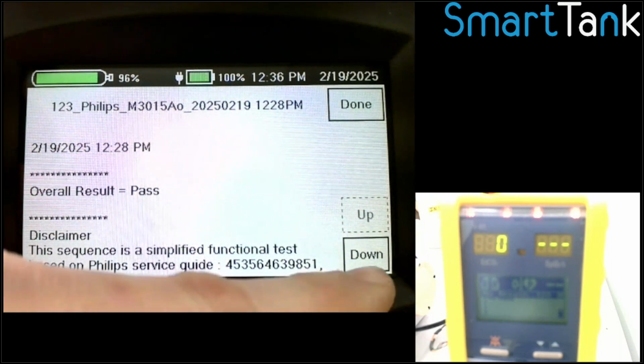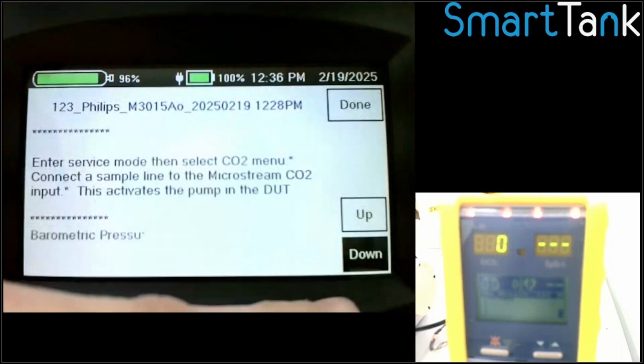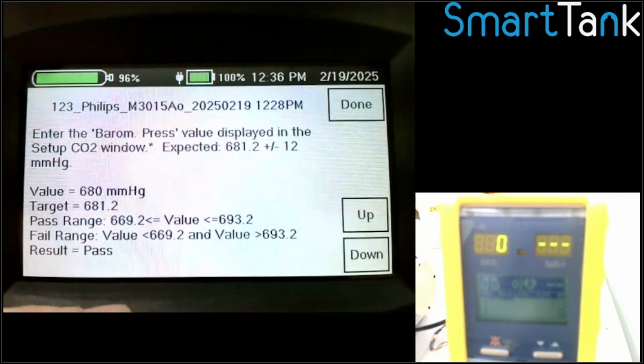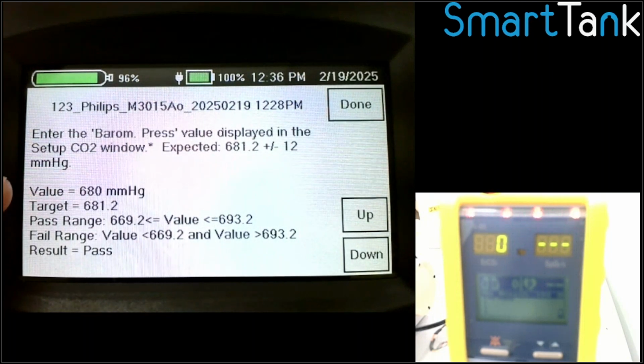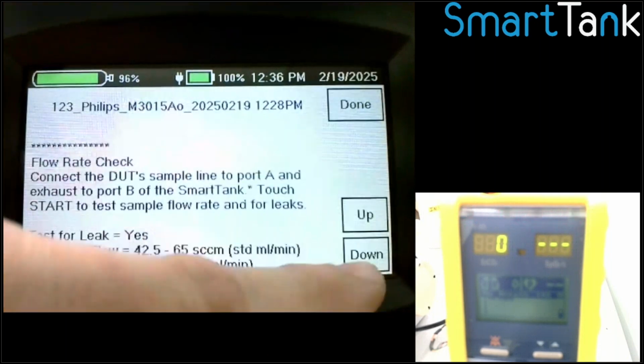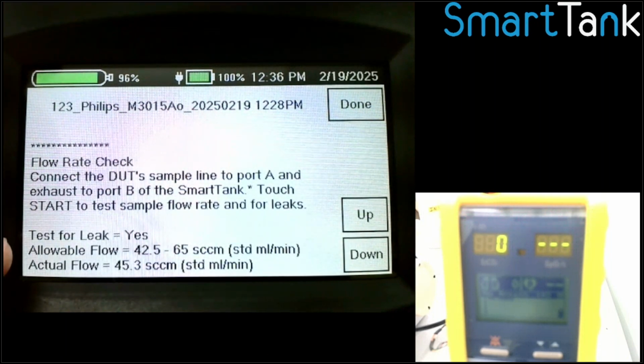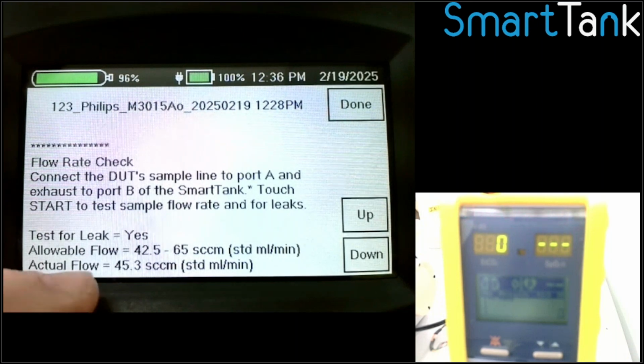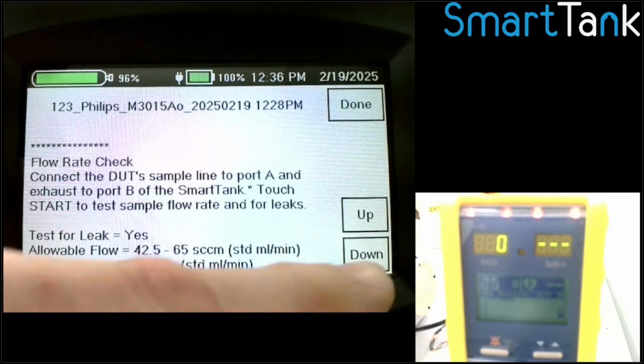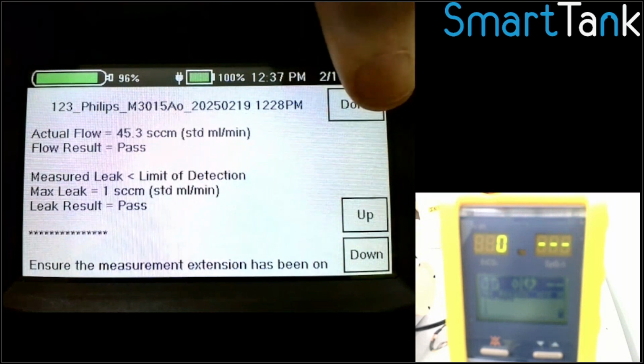This test report will have everything that I did, who did the test, what device I tested, all the values I entered, all the values the SmartTank measured, all the screens I went through. So in this case, I entered that 680 in and it was supposed to be 681.2 pass-fail criteria. There's the flow test where it measured at 45.3. It's interesting, this used to read about 50 and over the last year or two, it's slowly dropping closer to the point where it's failing. I don't know if we're wearing the pump out, but that's kind of been interesting to watch. And so this test report will have everything in it.